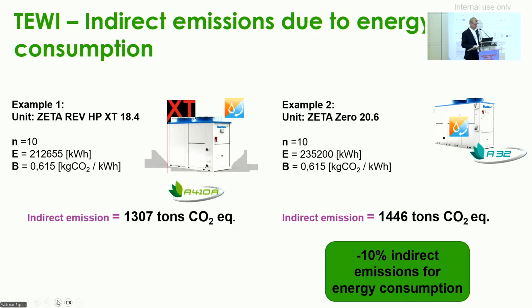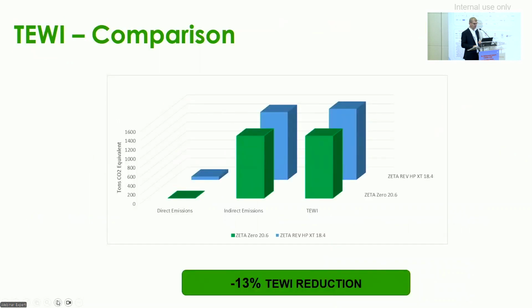The indirect emissions for energy consumption decrease by 10%. And this means that in terms of TEWI, we have a 13% reduction for the new unit compared to the legacy unit. This is an example within our product range, but of course the same principle can be used to compare different heat pumps from a sustainability point of view.